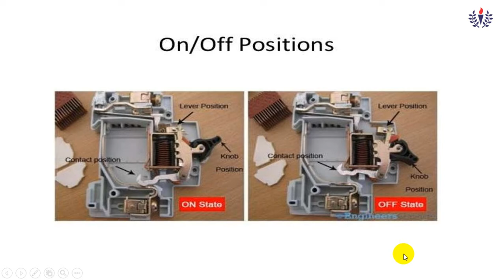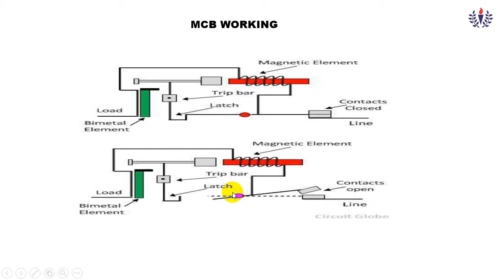So here you can see the contact points during normal operating conditions. The line will be coming inside. So this is the contact point. It will be moving in this direction to the load. But in case of any short circuit or overload, what will happen? This magnetic circuit will get magnetized and it will pull this contact, so it will get open. Otherwise, the bimetallic strip will bend here. So here this will pull the tripping contact. So once again this will open.